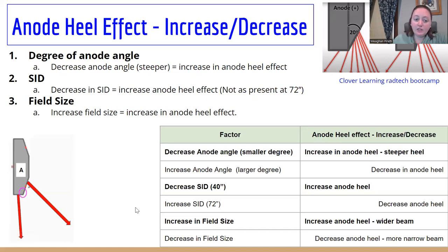So if you decrease your anode angle, we've already talked about that. You're going to increase your anode heel effect, a decrease in SID. So coming closer to the part will increase the anode heel effect. It is not as present at 72 inches as it is at 40.